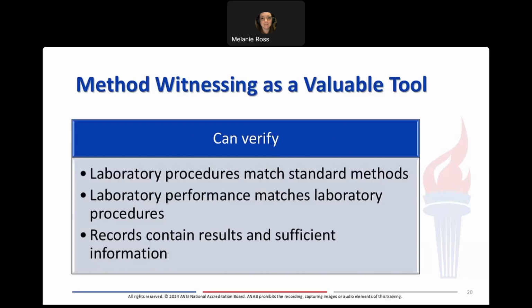Method witnessing can be a valuable tool, and it doesn't have to be implemented all or nothing. So you can determine how much of this method witnessing you want to incorporate into your internal audits to gather information and objective evidence to further improve your management system and technical operations. So we can verify that the laboratory procedures or organizational procedures match standard methods or industry methods or the source of that procedure. Then we can verify that laboratory performance matches the procedure. Then we look at those records that come out of that process and say, do the records contain the results of the activity being performed and sufficient information based on what is required by the procedure? So you can see we can gather quite a bit of information just by using our eyes and ears in the area where the work is being performed.